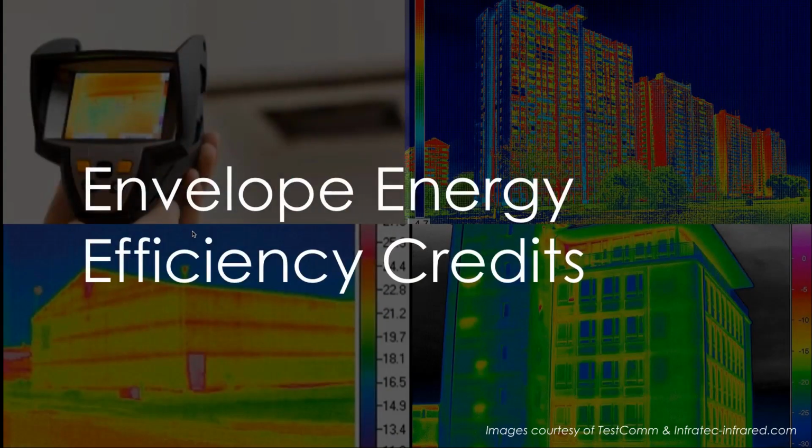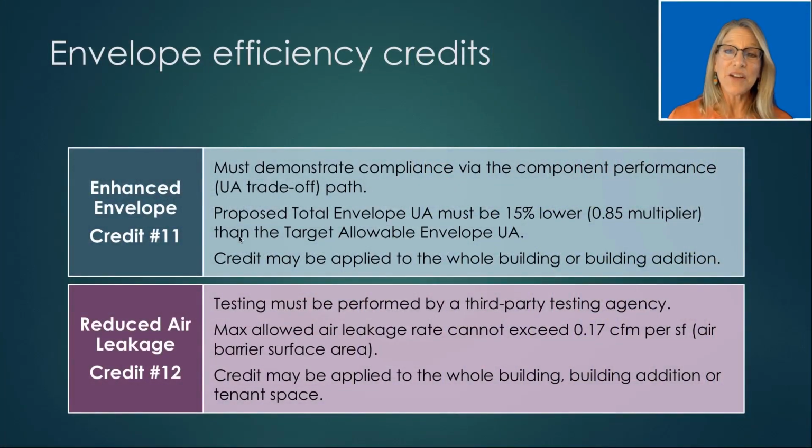Let's start with envelope. There are 2 envelope efficiency credit packages: enhanced thermal envelope performance and reduced air leakage. In a nutshell, to comply with the enhanced envelope credit, the project must demonstrate compliance via the component performance path or the UA trade-off path. The proposed total envelope UA must be 15% lower than the target allowable envelope UA. So you would be applying a 0.85 multiplier to the target allowed UA. This credit may be applied to the whole building or to the building addition.